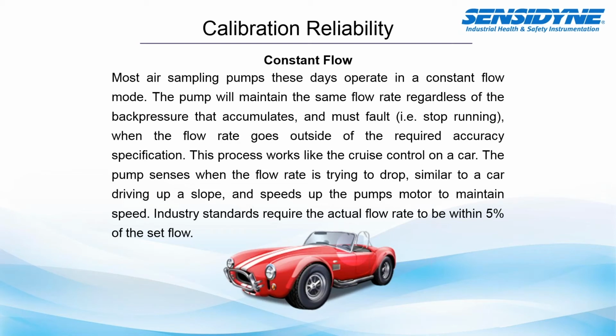So it's important to understand how constant flow works. Most air sampling pumps these days operate in a constant flow mode. The pump will maintain the same flow rate regardless of the back pressure that accumulates and must fault, i.e. stop running, when the flow rate goes outside the required accuracy specification. So usually that specification is 5%. So if I set my flow rate to, let's just say, 1 liter per minute, and I want it to be within 5% of that reading at all times, a constant flow pump will actually fault out if it goes outside of that plus or minus 5%.